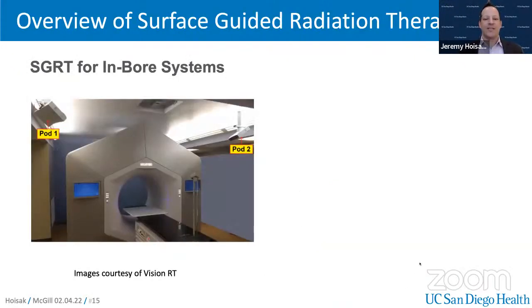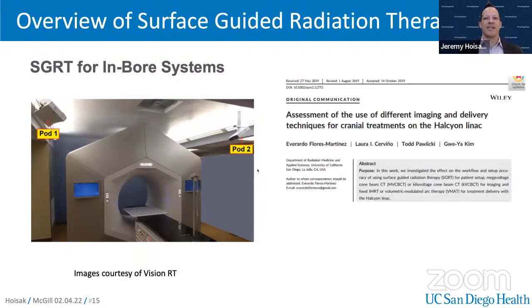Another interesting use of SGRT systems is for in-bore systems. Tomotherapy is sort of a gantry that's built in, so it looks like a CT scanner or an MRI. This here is the Varian Halcyon, which is also what we call a bore type gantry. So the gantry is actually within here. The linear accelerator rotates around the patient, similar to the way a CT scanner will rotate around the patient. Because it's entirely enclosed, the patient's not visible, so it's difficult to actually do SGRT with this system.